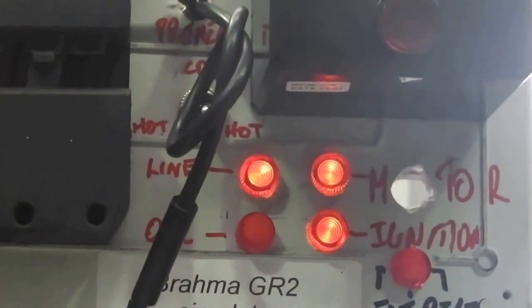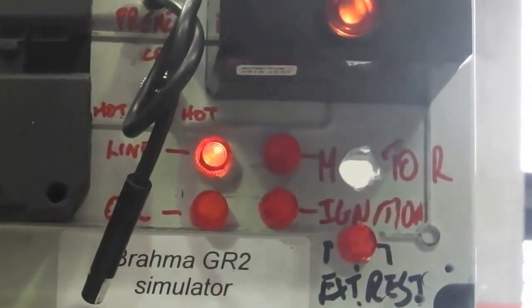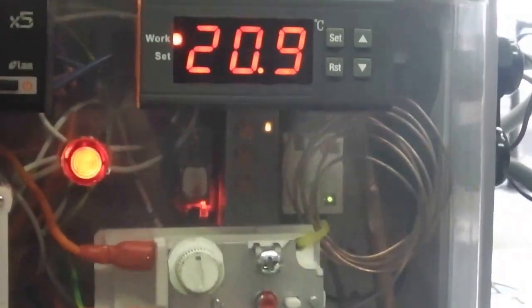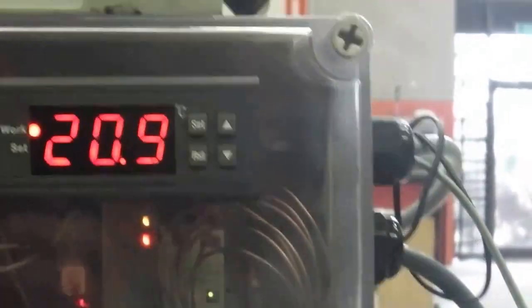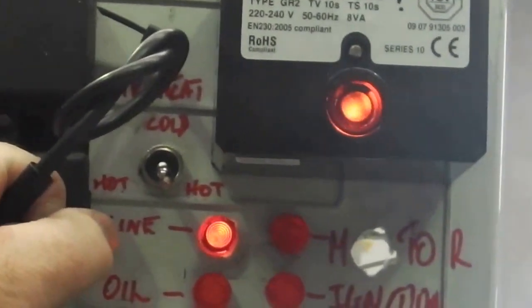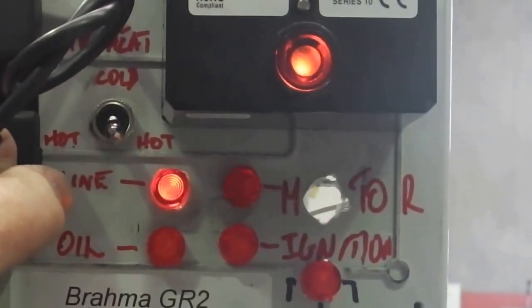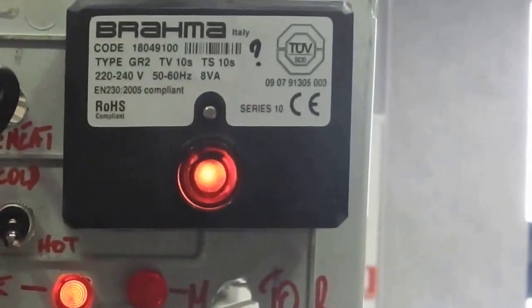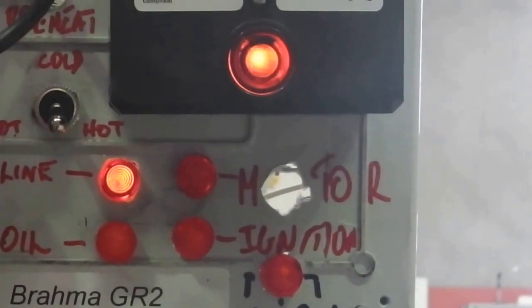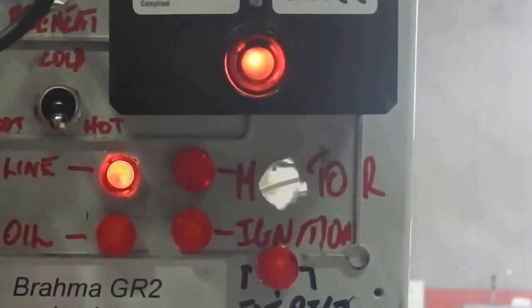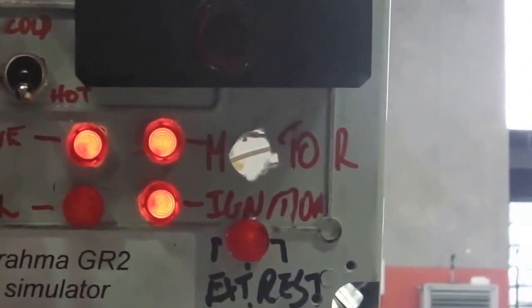So the gun's attempting to start up, got the line on and so on. So of course, with this simulator, we're deliberately getting it to fail re-ignition or restart all the time, but this time I'll let the automatic controller down below give it the automatic reset. Now I'll cover up the photoelectric cell, and the GR2 burner gun simulator fitted with the GR2 Brahma controller.